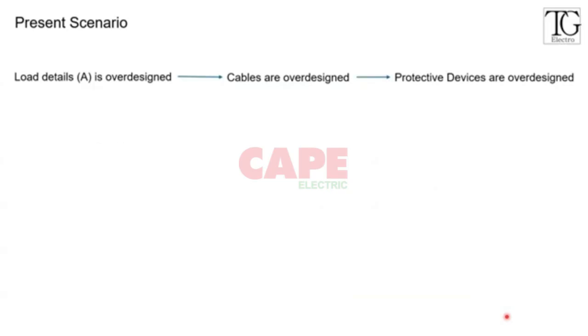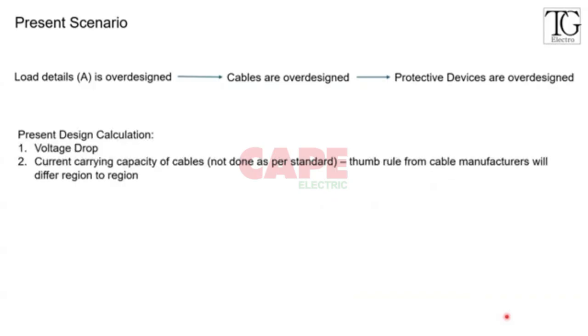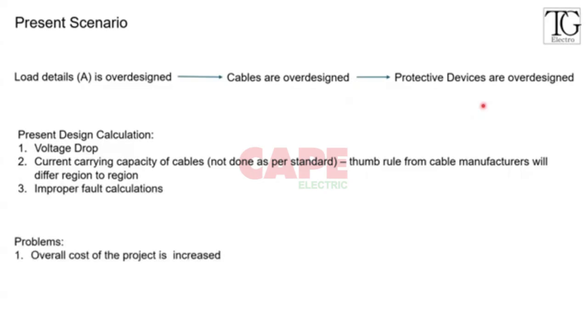And here, since we emphasize voltage drop more, and there are some cable manufacturers who give a thumb rule for the current carrying capacity of cables, and sometimes these differ from region to region, most of the time the cables are over designed, and the protective devices because of it are also over designed. One more point is improper fault calculations. So the overall cost of the project increases, and rather than the cost, which is much more important, the safety is compromised.